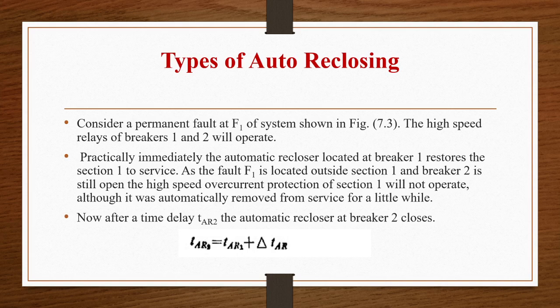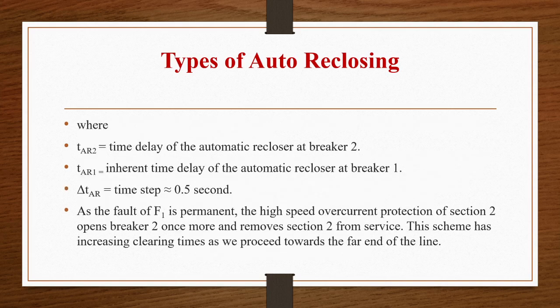As the fault F1 is located outside section 1 and breaker 2 is still open, high speed overcurrent protection of section 1 will not operate, and it was automatically removed from service for a little while, but still it will not operate. Now after a time delay, TAR2, automatic reclosure at breaker 2 closes, and our equation will become TAR2 is equal to TAR1 plus delta TAR, where TAR2 is the time delay of the automatic reclosure at breaker 2 and TAR1 is the inherent time delay of the automatic reclosure at breaker 1.